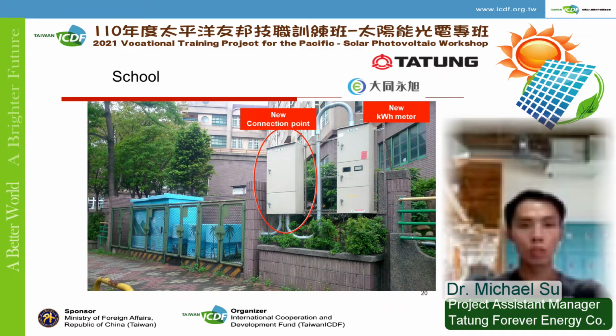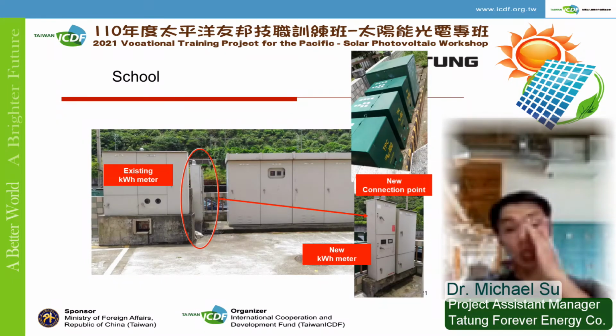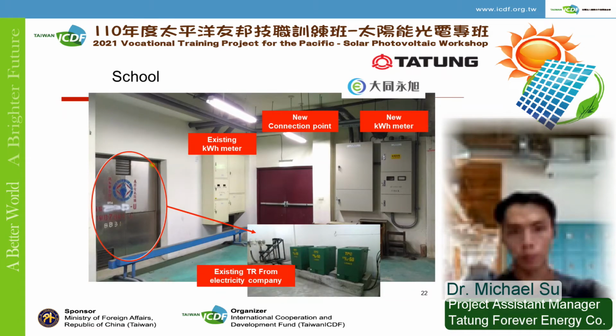Regarding the demarcation point, it's at the same place in this case, the copper bars inside our newly installed box. We also installed a new meter here for the purpose to calculate how much money TPC has to share with us. Some systems are like this, installed on ground surface. Then some are like this, all the boxes and equipment are installed in a basement. Usually you can find the TPC's distribution space in a basement. Their transformers will be inside the space. The rest is basically the same. We install a new meter and boxes with copper bars to do the connection and to mark demarcation point.